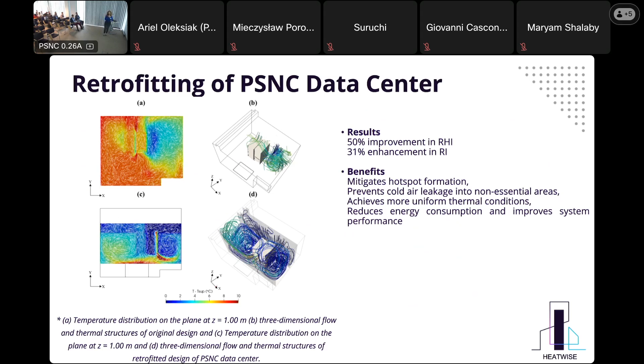What we did for PSNC data center, we did also add separator because server racks aligned with the fan coil outlets to reduce the airflow resistance and ensure efficient cold air delivery. And we introduced round racks to enforce hot aisle, cold aisle containment, preventing thermal mixing as well, and improving temperature uniformity to trap the cold air to the desired areas, actually, again.